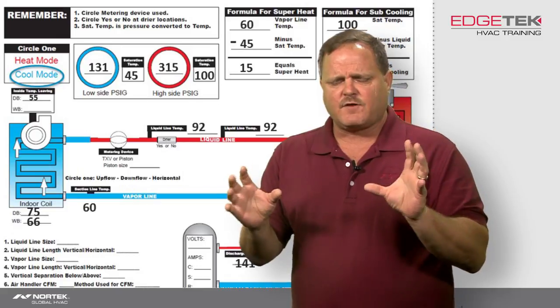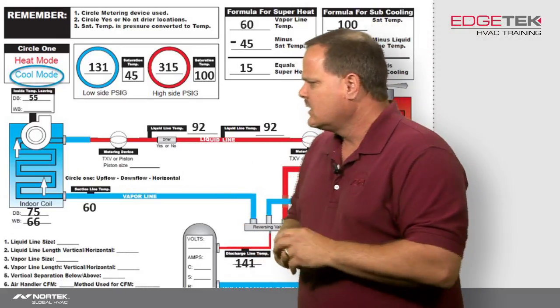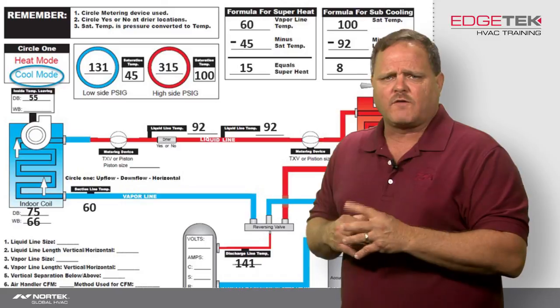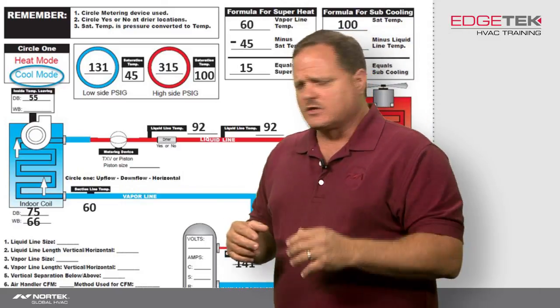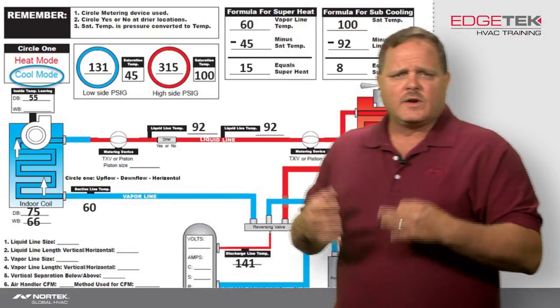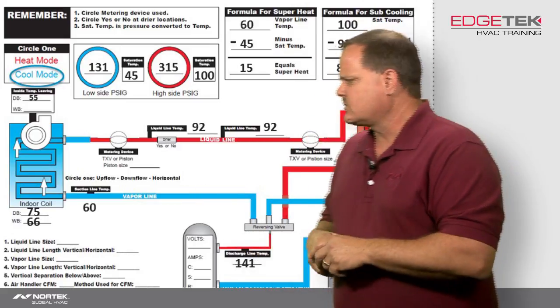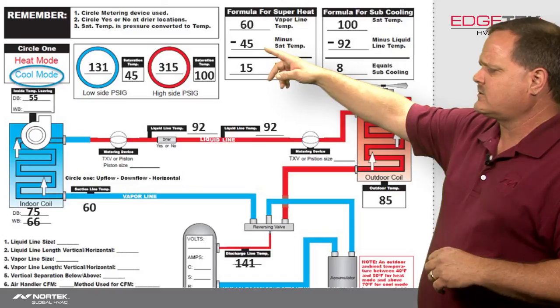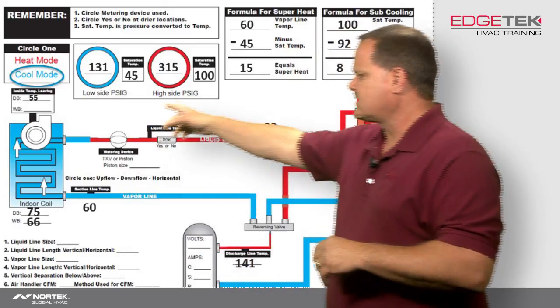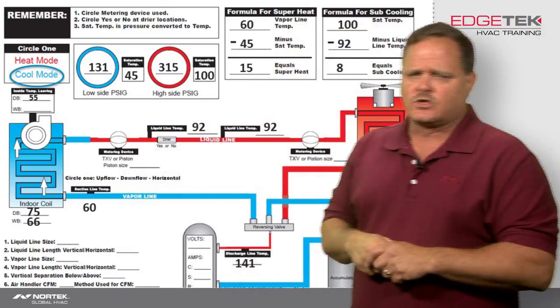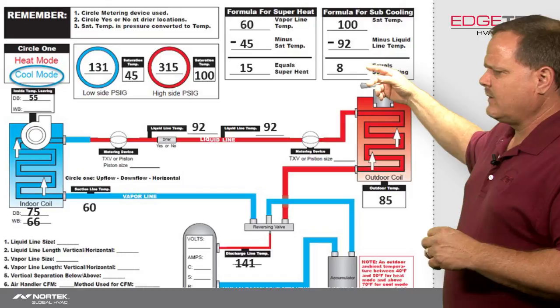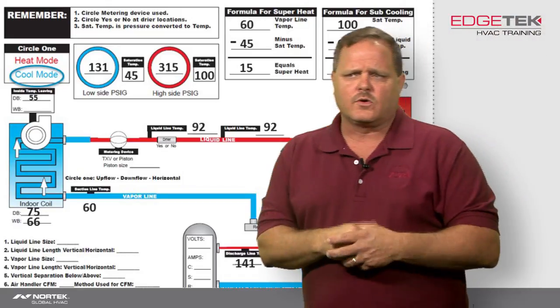Those are our two basic factors that make superheat and subcooling so important. The required superheat has to be determined from a slide calculator, which I've already done prior to this video. With that 66 degree wet bulb and the 85 degree outdoor temperature, we need a required superheat of 15 degrees. For this system, I've got a 60 degree suction line temperature, minus that 45 degree evaporator temperature, which gives me 15 degrees of superheat — perfect. On the other side, subcooling is 100 degree condensing temperature minus 92, giving me 8 degrees of subcooling.